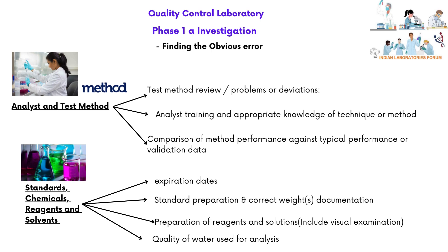Phase 1a investigation to find out the obvious error will include: review of analyst and test method details, review of the test method used, problems or deviations occurred, analyst training, competency, and appropriate knowledge of the technique or method used for testing. Comparison of method performance against typical performance such as spike recovery or validation data. Review of standards, chemicals, reagents, and solvents used in testing, including expiration dates, standard preparation, and correct weights documentation. Preparation of reagents and solutions, including visual examination and quality of water used for analysis.